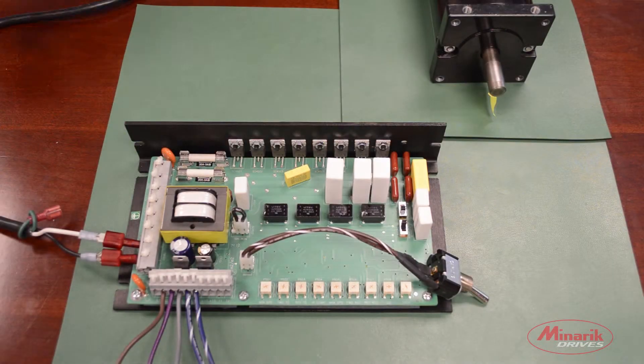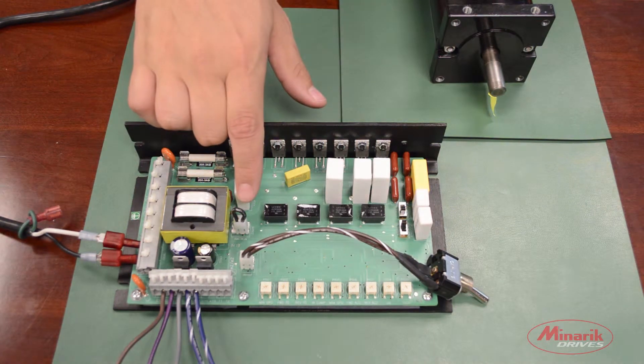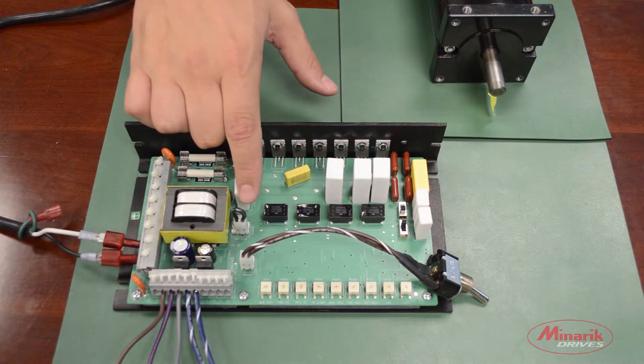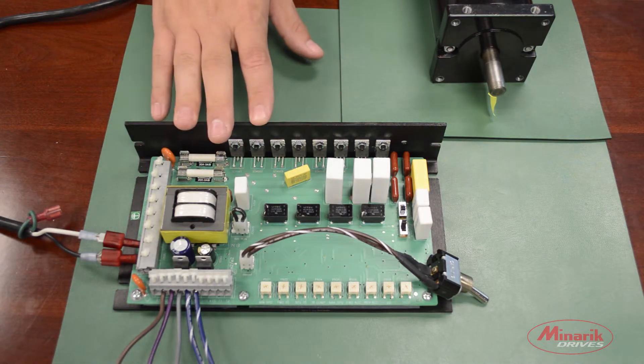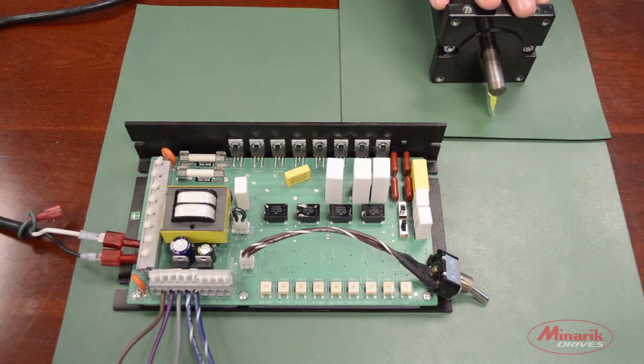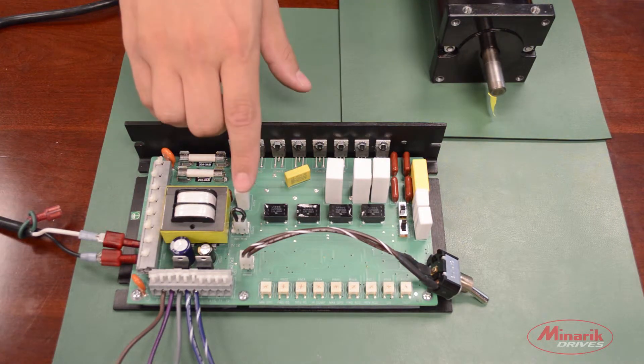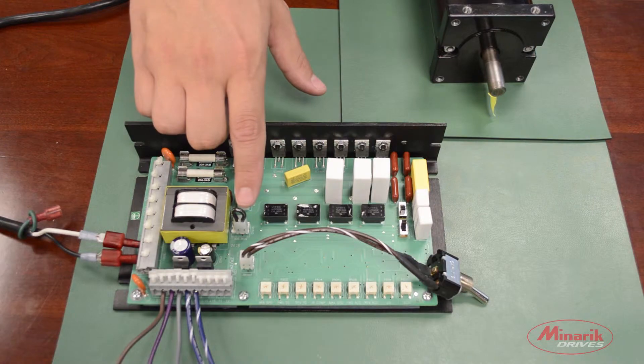Next we'll look at the jumper located next to the transformer on the drive. This sets whether the drive is in run mode or coast to stop mode. In coast to stop mode the drive will disconnect the motor from power and let it coast to stop. So to operate the drive we need to have the drive in run mode which is the factory default setting.